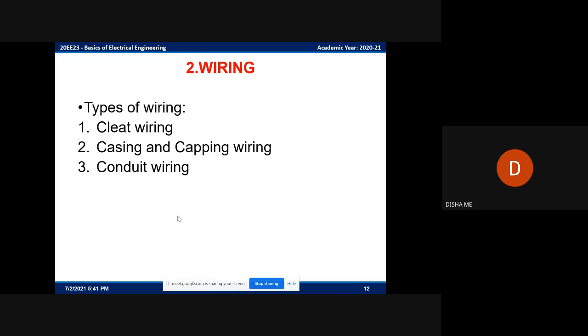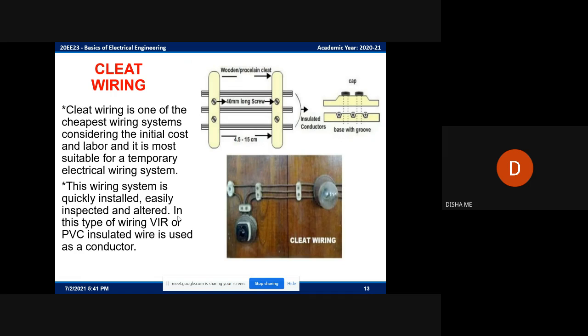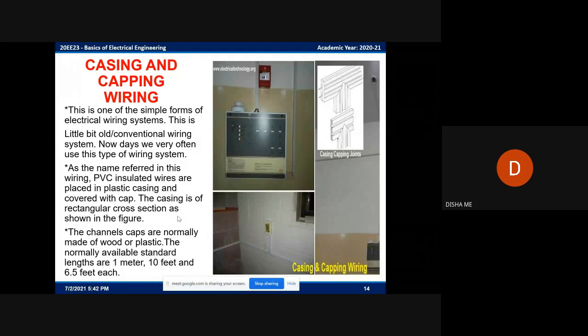Wiring. Types of wiring: cleat wiring, casing and capping wiring, conduit wiring. Cleat wiring is one of the cheapest wiring systems considering the initial cost and labor, and it is most suitable for a temporary electrical wiring system. This wiring system is quickly installed, easily inspected and altered. In this type of wiring, VIR or PVC insulated wire is used as a conductor.